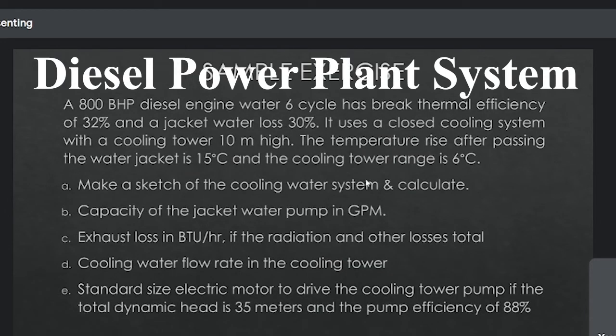So, yung sample exercise natin, 800 brake horsepower diesel engine, water 6 cycle, has a brake thermal efficiency of 32% and a jacket water loss of 30%. It uses a closed cooling system with a cooling tower 10 meters high. The temperature rise after passing the water jacket is 15 degrees Celsius and the cooling tower range is 6 degrees Celsius.